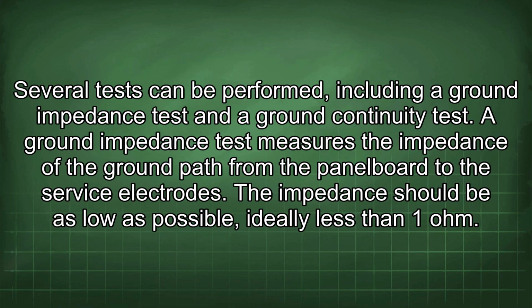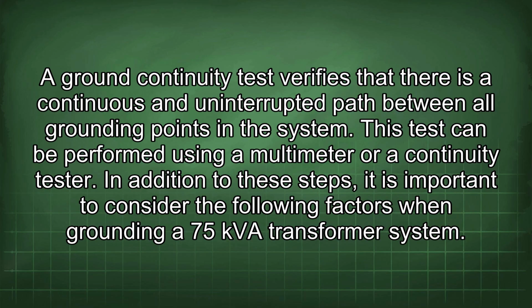Several tests can be performed, including a ground impedance test and a ground continuity test. A ground impedance test measures the impedance of the ground path from the panel board to the service electrodes. The impedance should be as low as possible, ideally less than 1 ohm. A ground continuity test verifies that there is a continuous and uninterrupted path between all grounding points in the system. This test can be performed using a multimeter or a continuity tester.